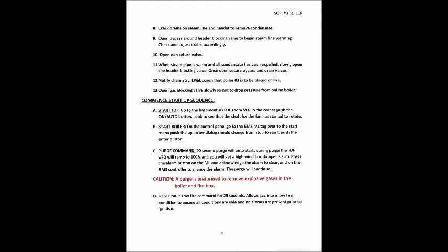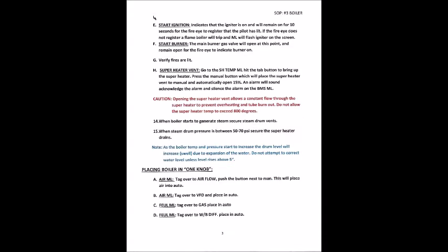D. Reset MFT. Low fire command for 25 seconds. Allow gas into a low fire condition to ensure all conditions are safe and no alarms are present prior to ignition. E. Start ignition. Indicate that the igniter is on and will remain on for 10 seconds for the fire eye to register that the pilot has lit. If the fire eye does not register a flame boiler will trip and ML will flash igniter on the screen.